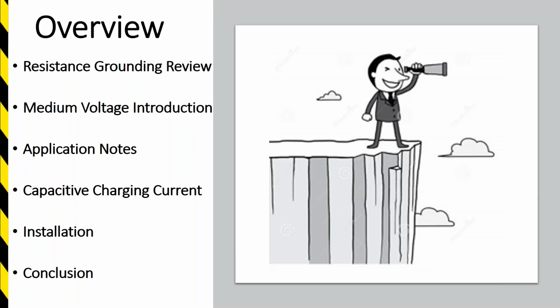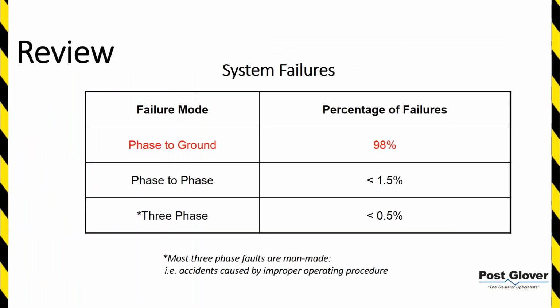Let's go ahead and start with the review. So this is kind of standard across all types of resistance grounding, but usually when you're looking at system failures, whether it be industrial, I've seen reports, or I should say studies in utilities as well, the vast majority of all your faults are going to be phase to ground. It could be 95, it could be 98, depending on the study you're looking at. The point is the vast majority of them are phase to ground. The other categories are phase to phase, three phase.